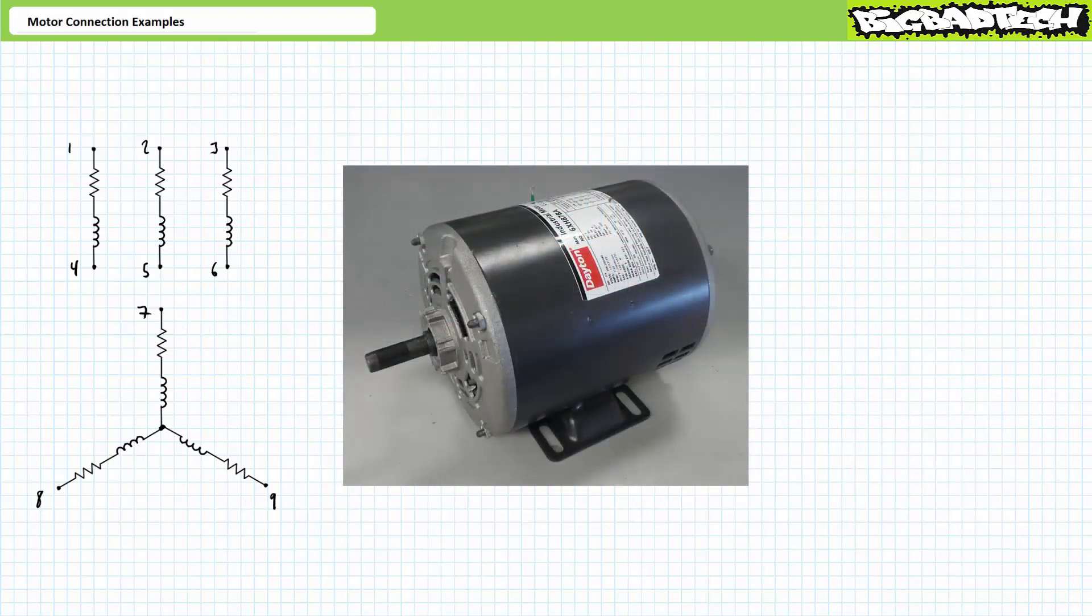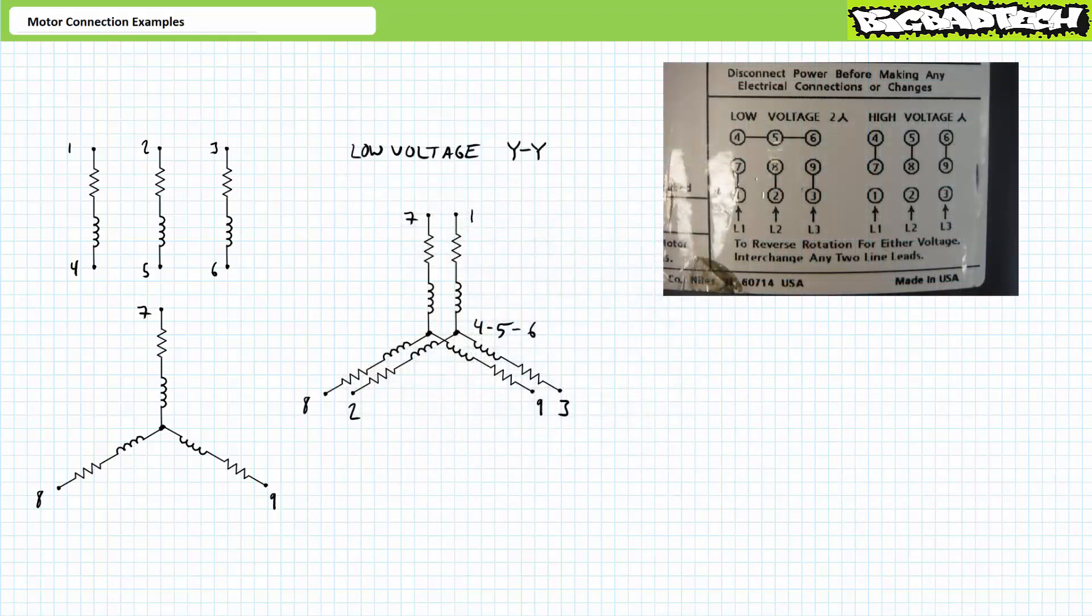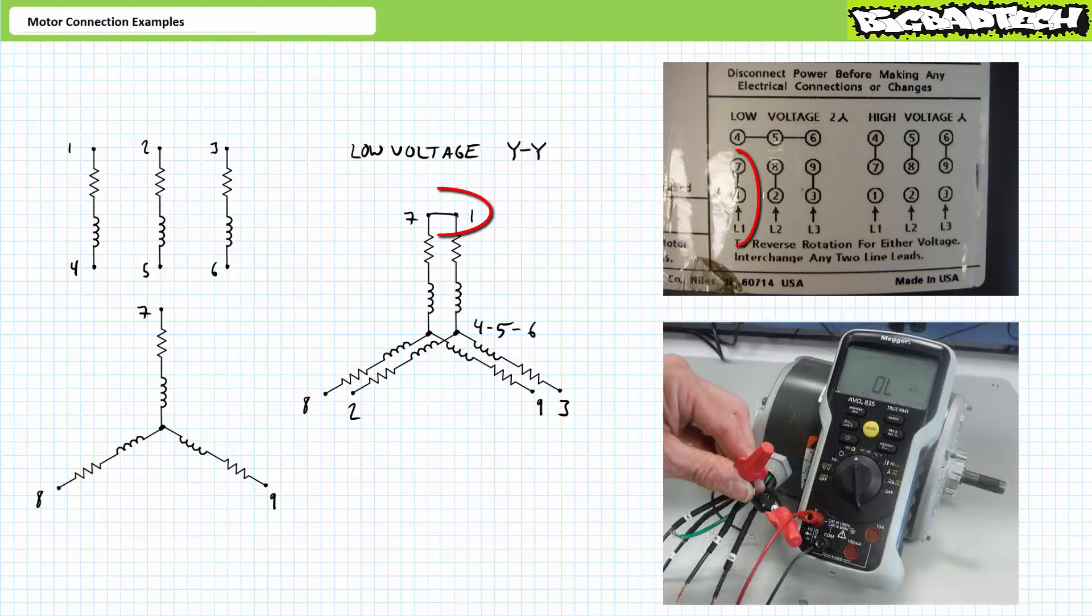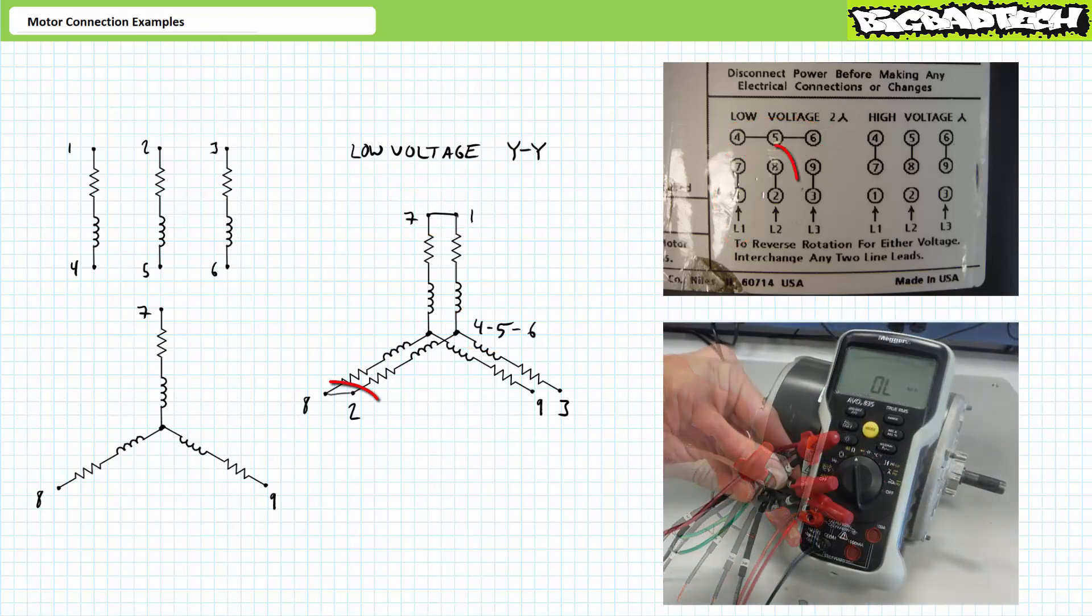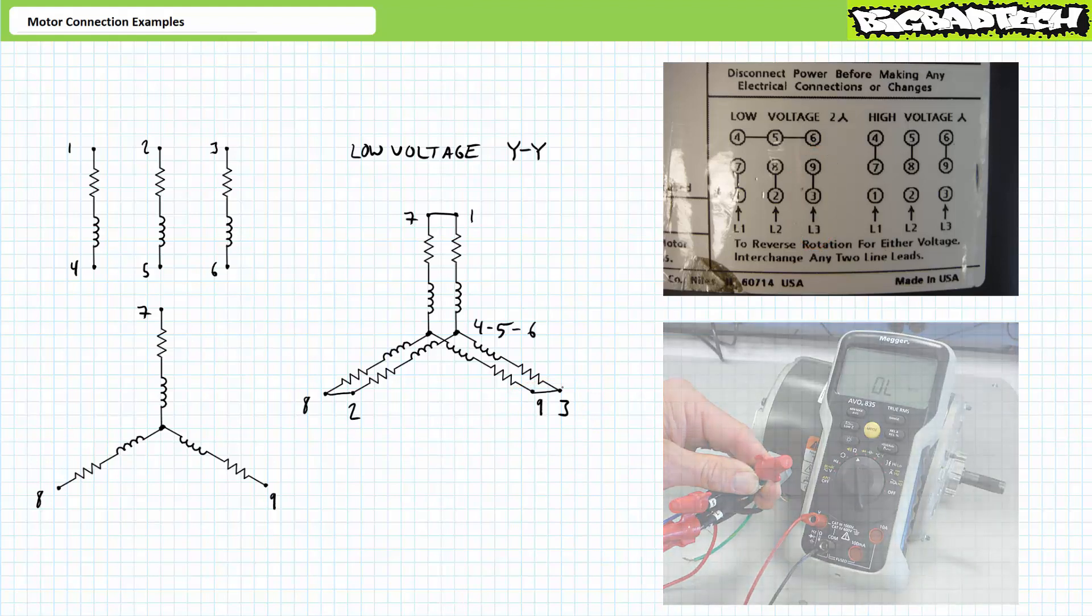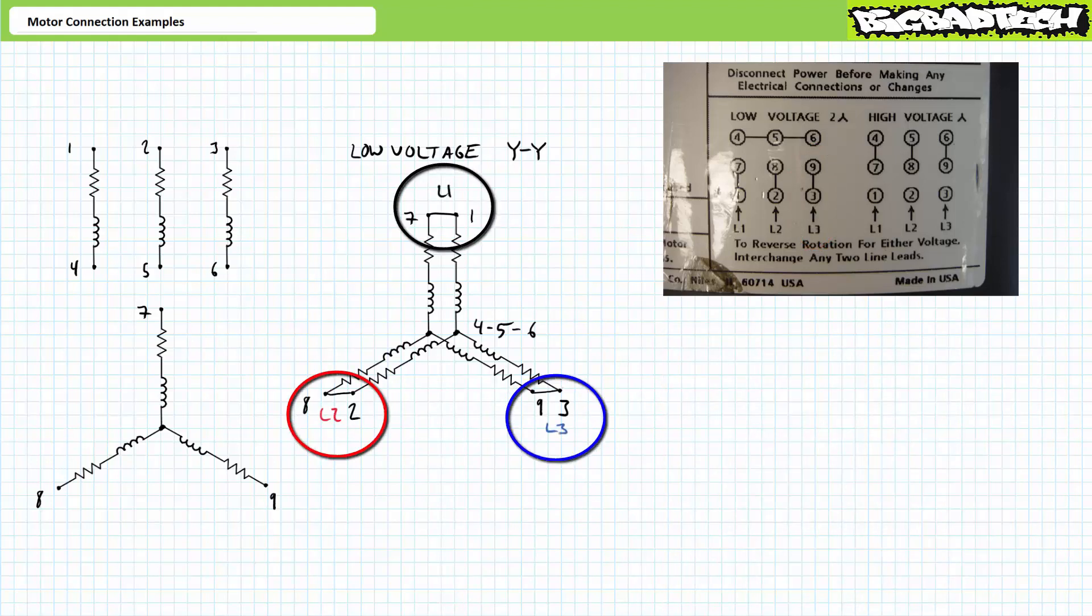This is indeed a nine-lead Y configured motor. Let's use the connection diagram to set it up in low voltage configuration. The motor connection diagram on the motor nameplate specifies a low voltage YY configuration requires leads four, five, and six to be tied together forming another Y. Then one is tied to seven, two is tied to eight, and three is tied to nine forming an almost overlapping double Y in parallel with one another. Primary lines L1, L2, and L3 would be connected to conjoined terminals one-seven, two-eight, and three-nine.